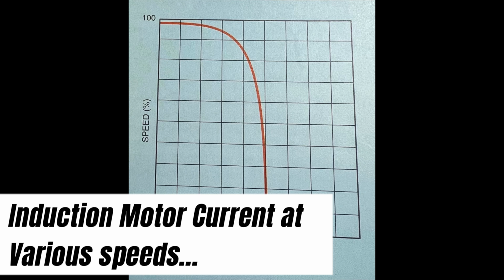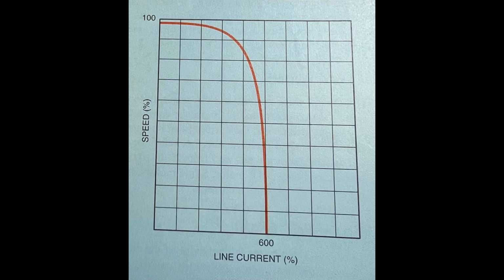First, note that the starting current is high compared to the running current. In addition, the starting current remains fairly constant at a high value as the rotor speed increases. The current then drops sharply as the motor approaches its full rated speed. Since the motor heating rate is a function of I squared times R, or copper loss, this rate is high during acceleration. For most of the acceleration period, the motor can be considered to be in the locked condition.